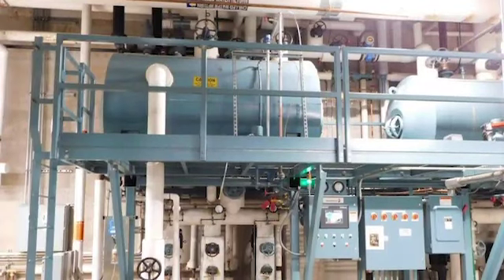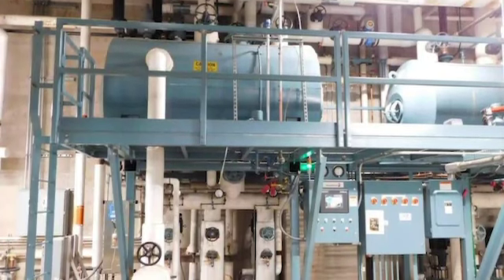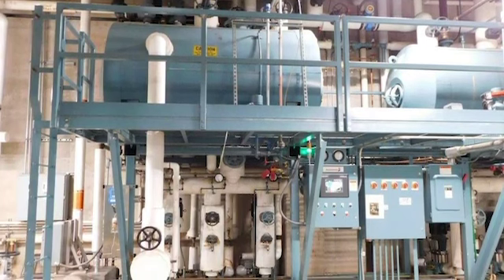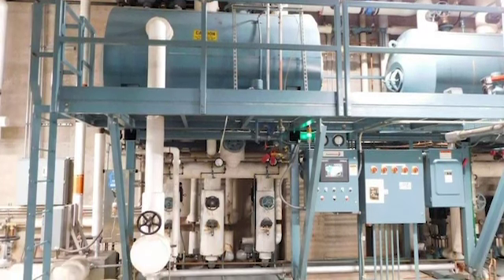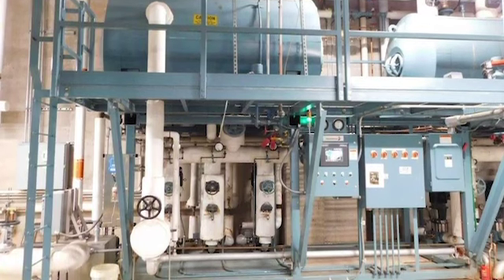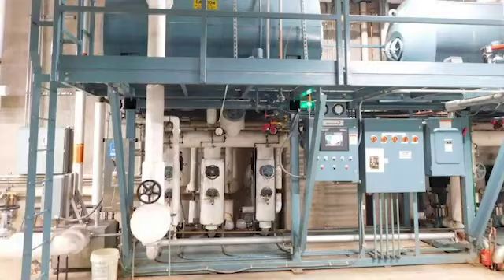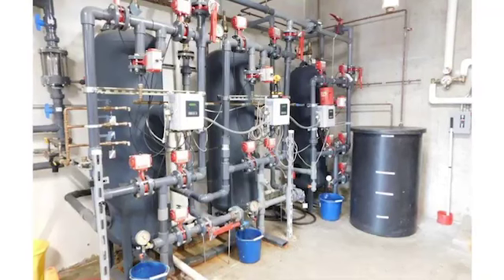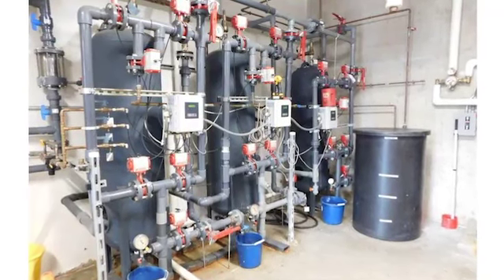Take a quick peek here at the deaerator. It's a 5 PSI, typically deaerating feed water heater, and a surge tank over there to the right, where all the hospital returning condensate comes back. During the normal part of the year, we're better than 90% condensate return typically. In the winter, the hospital does direct steam injection for humidification, so we can lose up to 15,000 pounds an hour of steam to humidification in the winter and the really dry days. So we do have to bring in a little bit of makeup water for that purpose.